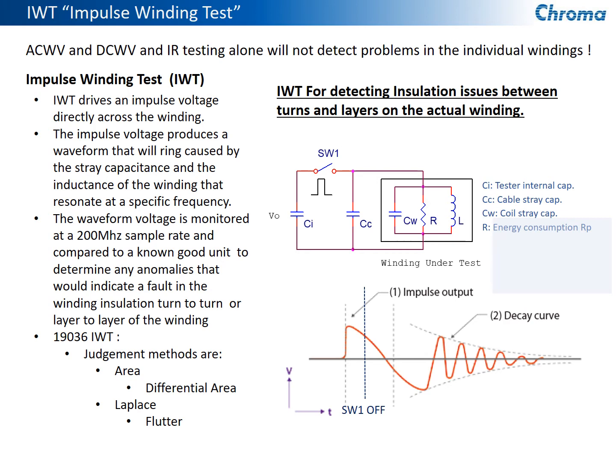We do a Laplace calculation based on the entire waveform, and also flutter. And by doing this, we can do a very good analysis of that winding to make sure it meets all the requirements, and there's no faults within the winding when we compare it to a known good unit.